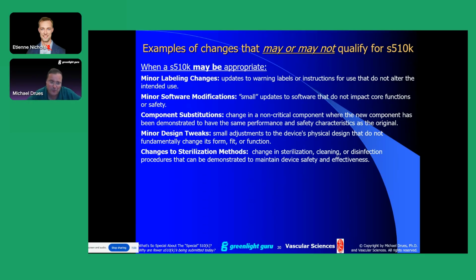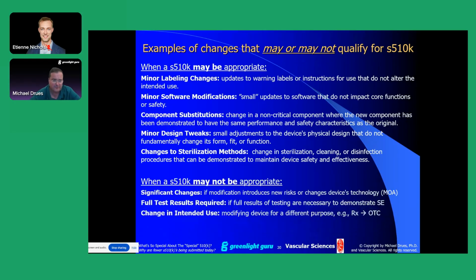And finally, changes to sterilization methods. Now, this you have to be really, really careful about, because if you change sterilization, cleaning, or disinfection procedures and don't demonstrate that they maintain device safety and effectiveness, you can get into big trouble. As those of you who have listened to my podcast know, I work as an expert witness in medical device product liability cases. Suffice it to say, there was one of the largest class action lawsuits in the history of the medical device industry, in which I was an expert witness, involving certain hip and knee replacements by a particular manufacturer. Long story short, one of the root causes of that lawsuit was improper changes to their sterilization methods. So this one is easy to say on a PowerPoint slide, but the consequences can be very significant.